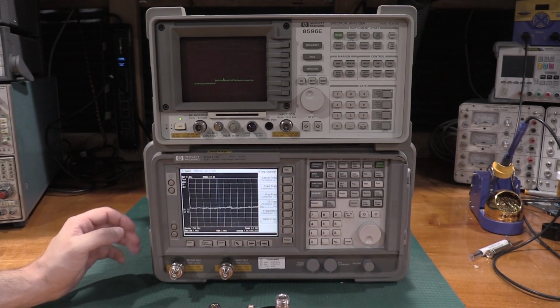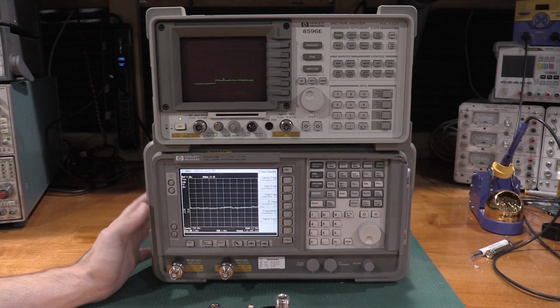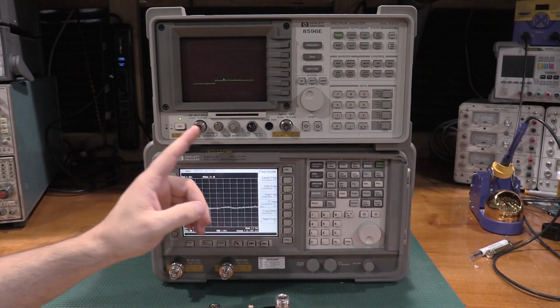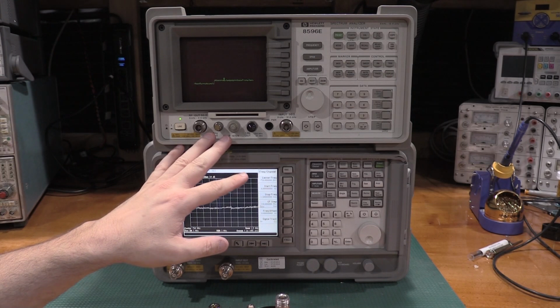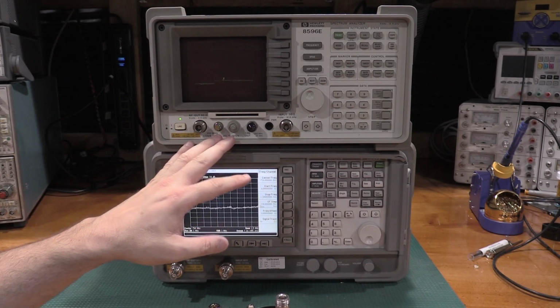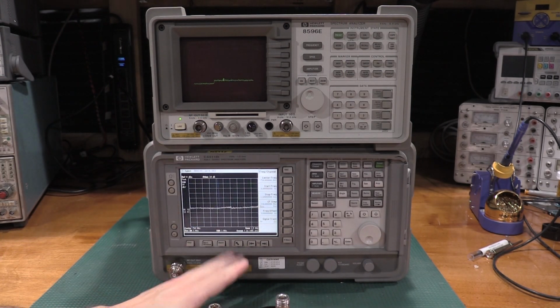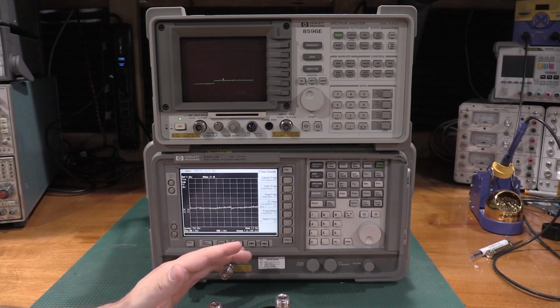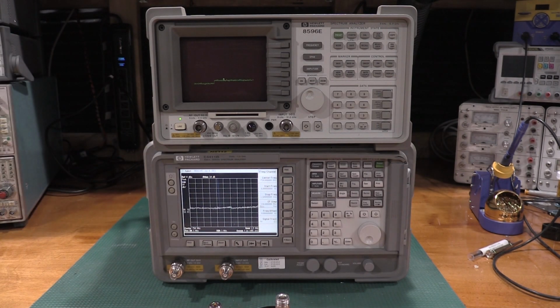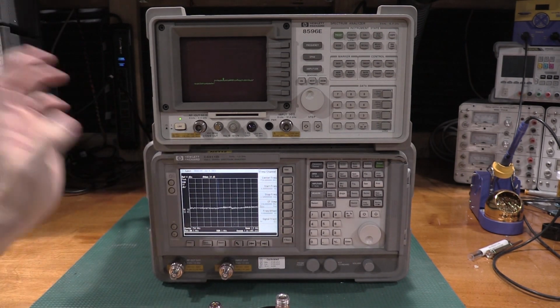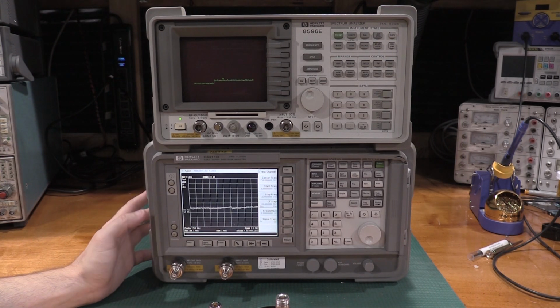I'm going to let these warm up, because they have to warm up for 30 minutes before you run them through their calibration procedures. This has some cables that we need to hook up to the front end, and let them run through the calibration. This will do the calibration internally. As I was waiting for them to ship in, I was pretty excited, so I was poking around in the manuals and getting familiar with the units.